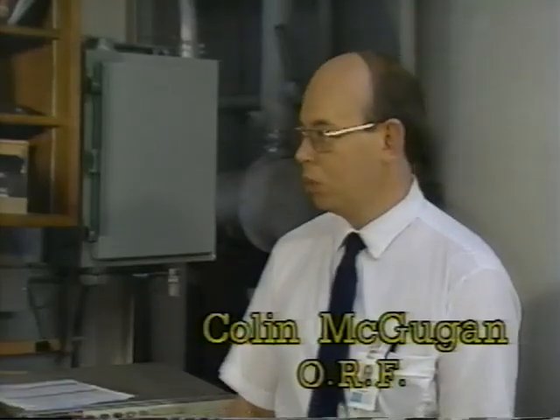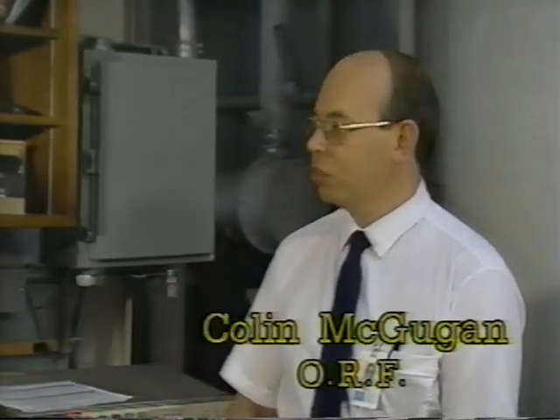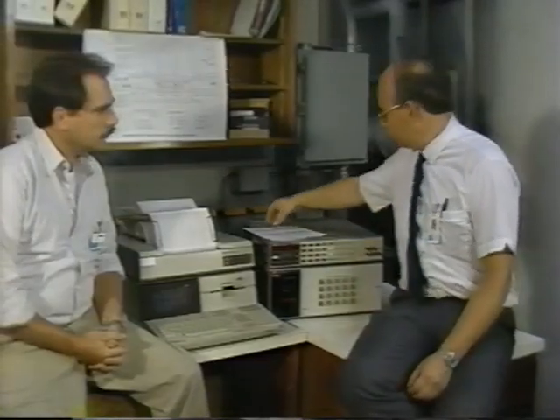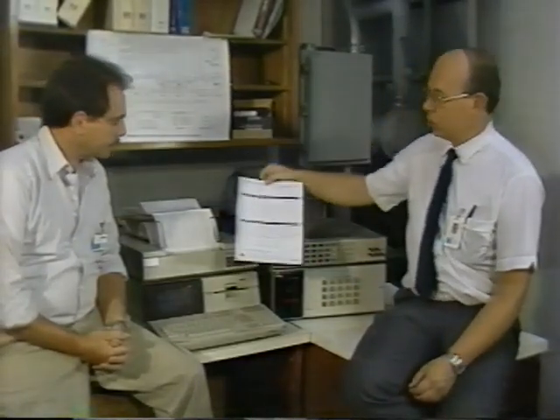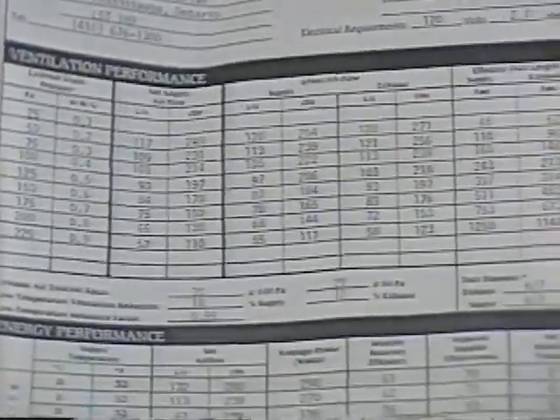And what are you testing them for? We test the airflow and the efficiency of the units at 0 degrees C and at -25. We also look at the defrost characteristics of the unit at -25, see whether it plugs up with frost and how it's operating. It's pretty thorough. How many units have you tested? We've tested about 25 so far. And is there any information available to builders regarding the tests? Yes, all the information from the testing is summarized on this specification sheet. This is prepared for the R-2000 program and published by them. And it's available also through the manufacturers, I suppose? Yes, they distribute it out to the manufacturers and through their local offices.